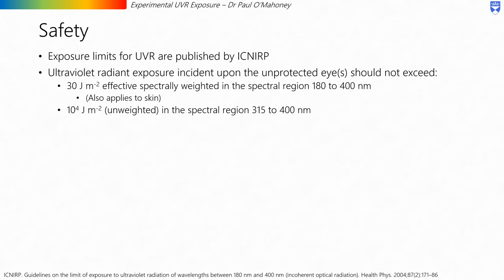Safety is of course very important as UVR can present a hazard to human health. Exposure limits for UVR are published by the International Commission for Non-Ionising Radiation Protection and are summarised as follows. Ultraviolet radiant exposure incident upon the unprotected eyes should not exceed 30 joules per metre squared effective spectrally weighted in the spectral region of 180 to 400 nanometers, and 10 to the power of 4 joules per metre squared unweighted in the spectral region of 315 to 400 nanometers. Both of these criteria must be met, and the first limit also applies to exposure incident upon the skin.